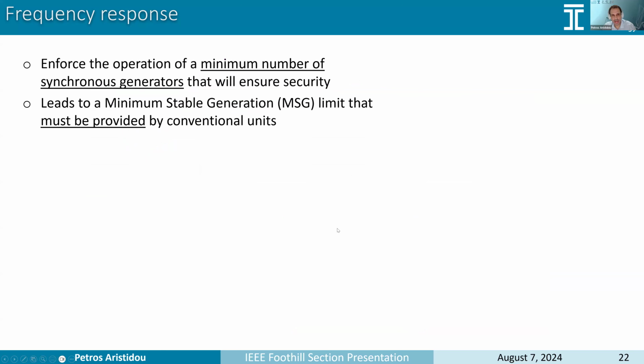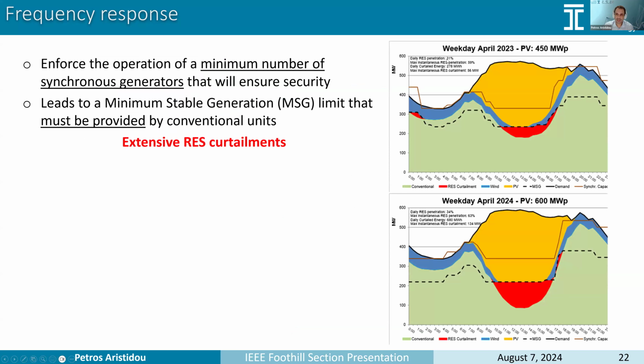How does the system operator handle this? At this moment, what they do is that they enforce the operation of a minimum number of synchronous generators in order to ensure that you have enough inertia and enough frequency containment reserves in order to make sure that situations like this don't happen. But if we have a minimum number of synchronous generators, this translates to a minimum stable generation limit. So this is the minimum amount of power that the conventional units must provide in order to be stable.